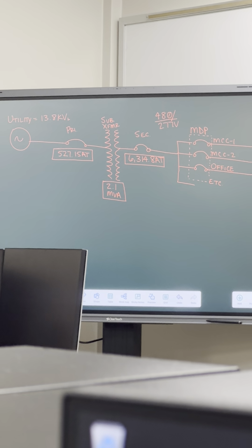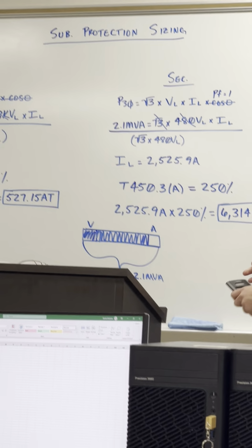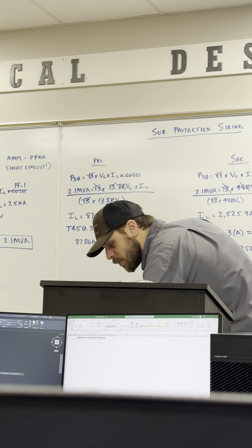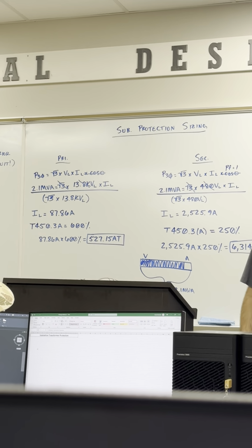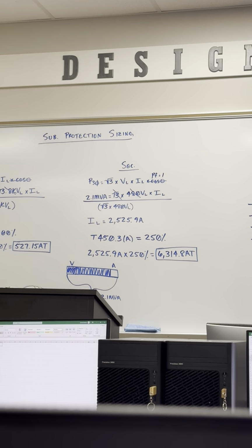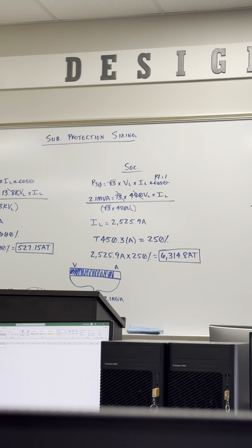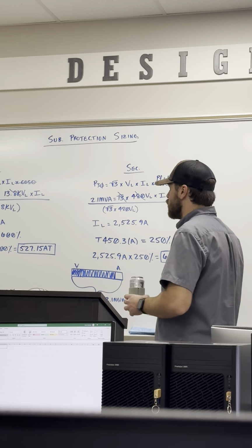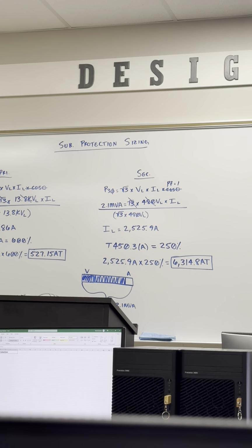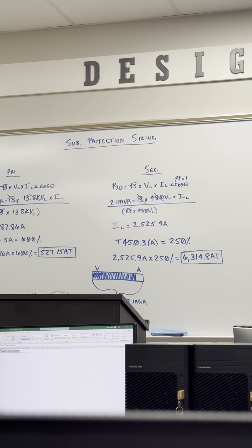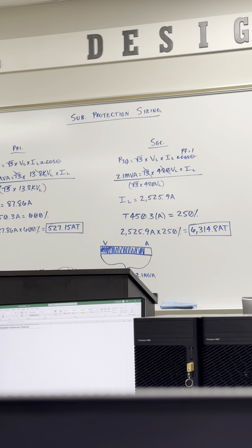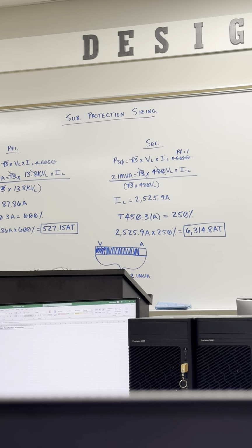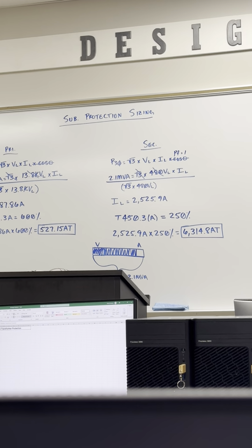So the same thing applies to that primary side. That's not going to be a fixed trip breaker. That's an adjustable breaker. So again, it's probably more accurate to say that that is our calibration setting for our breaker rather than the breaker size. But that's what we're going to calibrate that adjustable breaker to, about 527 amps there. So once you get that calculated value, whatever that number is, those are those settings. So that's what we're going to record.